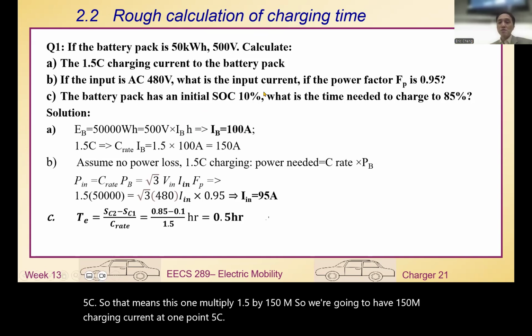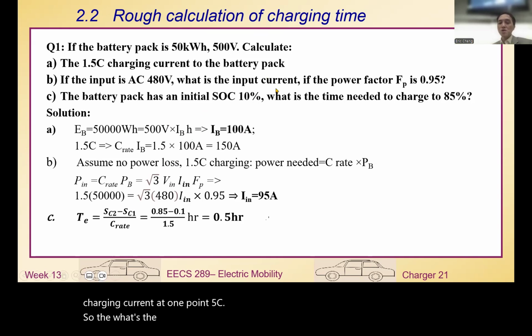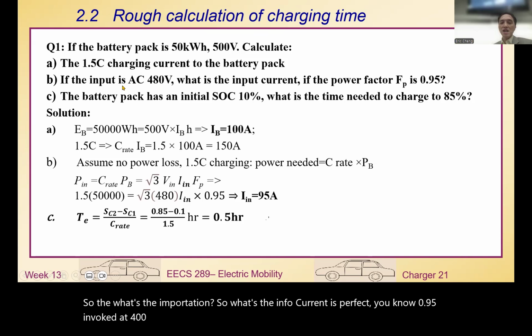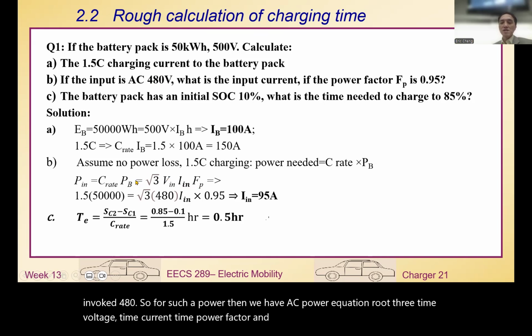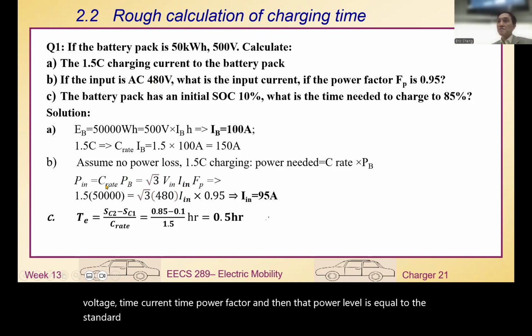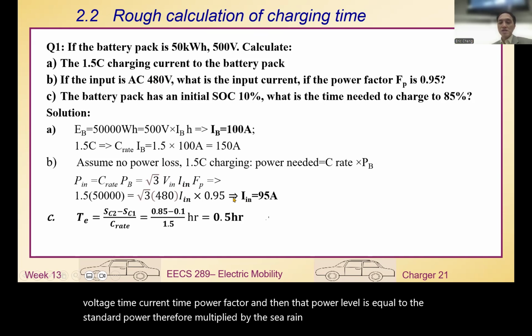So given the input voltage of 480 volts and power factor of 0.95, for three-phase AC power we use the equation: power equals √3 times voltage times current times power factor, where that power level equals the standard power level multiplied by the C rate. Calculating this gives an input current of 95 amps.